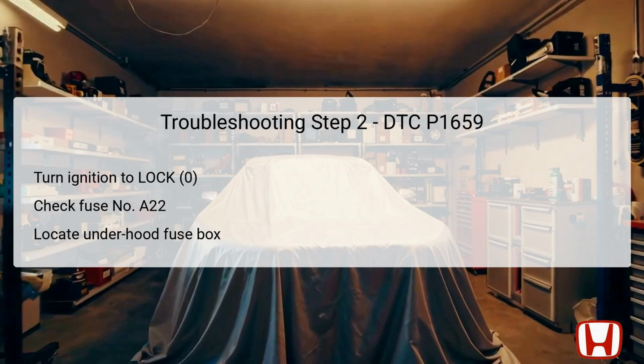If the fuse is confirmed to be okay, the troubleshooting can progress to testing the ETCS control relay in the next step. If the fuse is blown, addressing this fault would be the immediate priority before investigating further.